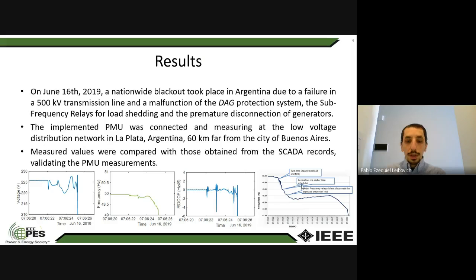As I mentioned before, the PMU performance during the 2019 Argentinian blackout was also analyzed. On June 16, 2019, a nationwide blackout took place in Argentina. The system was operating within its limits, with a demand of approximately 13,200 megawatts, when a failure in a 500 kilovolt transmission line took place. A malfunction of the automatic generation disconnection protection system, that is the DAG protection system, failures in the sub-frequency relays for load shedding, and the premature disconnection of generators were the causes for the system collapse. These failures can be seen in the event sequence shown in the image below.